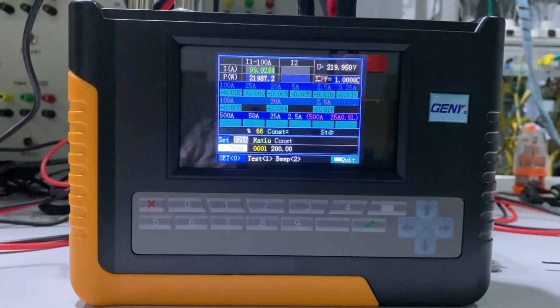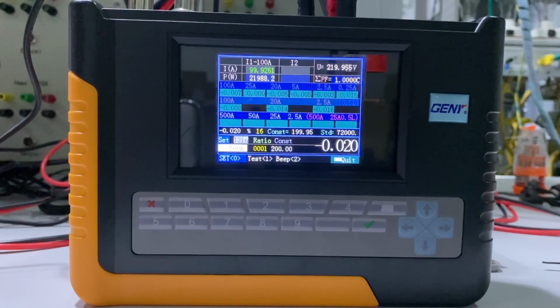The number of pulse cycles is automatically defined. The time it takes to calculate each error is also automatically defined. The first error is displayed. It is relatively high, so we have to wait for the second error to come, until the error is shown in red or is less than 0.05%. Then we can move to the next calibration point.